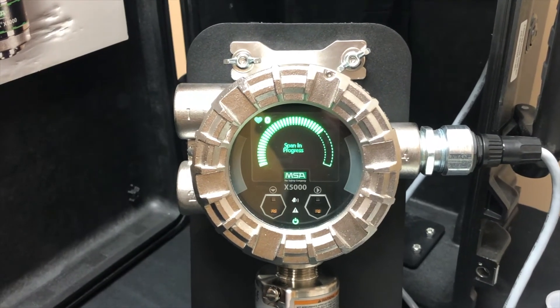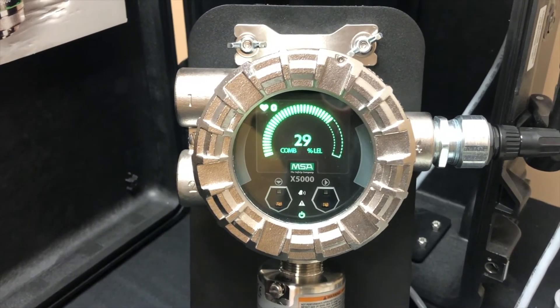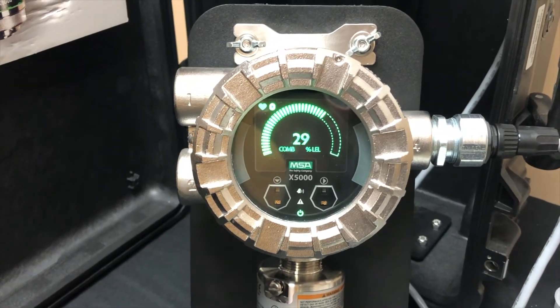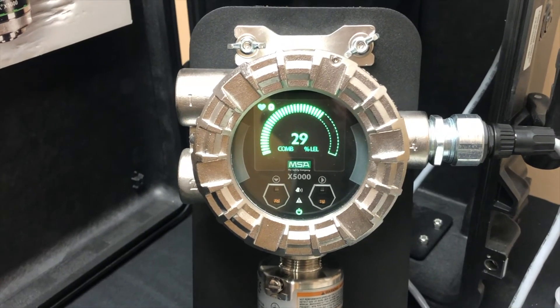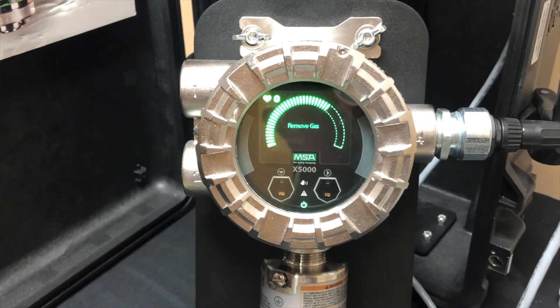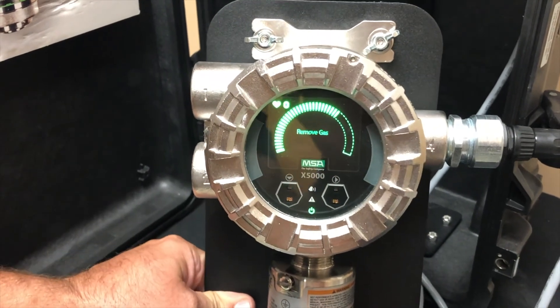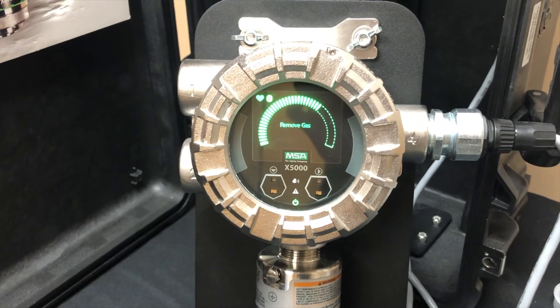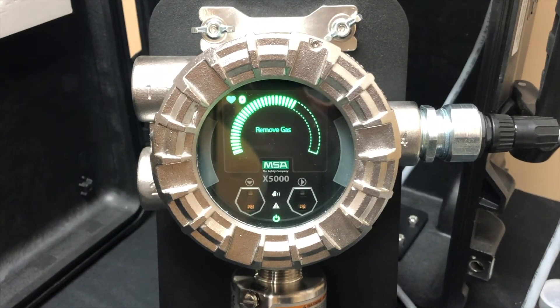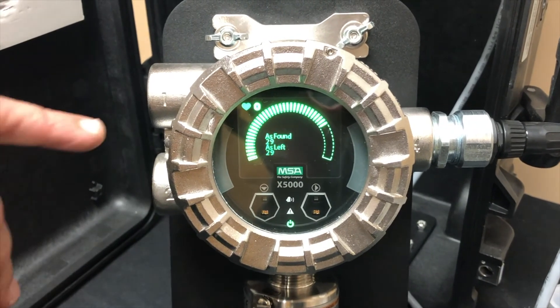You can see it's at 29. Once it gets a stable measurement and holds that for about 15 seconds, you'll see a message that says span successful and to remove the gas, and then it will store that data. It'll also tell you what it was found at and what it left it at. So if it stays at 29, it would say found at 29, left at 29. You can also go back in and look at the previous calibration. You can see the remove gas signal — we're going to take our gas off. It will show you what it was found at and what it left it at — it's basically finalizing the calibration.